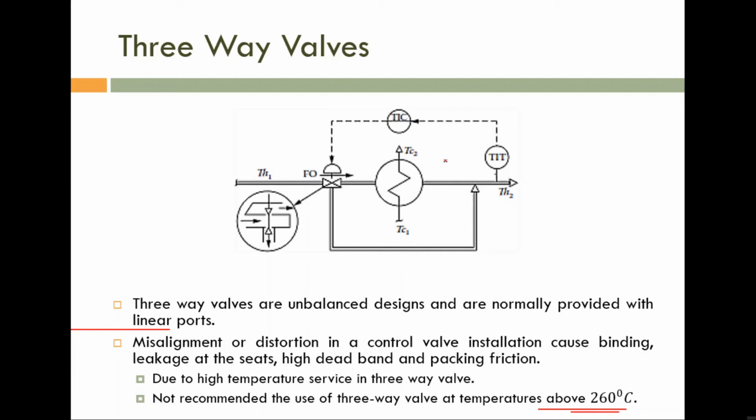So what about the static resistance? Definitely this heat exchanger will provide some static resistance. This one doesn't have that static resistance. So definitely it will provide some unbalance. This three-way valve is providing one unbalance. Along with that, due to this resistance, the flow rate has an additional unbalanced condition.